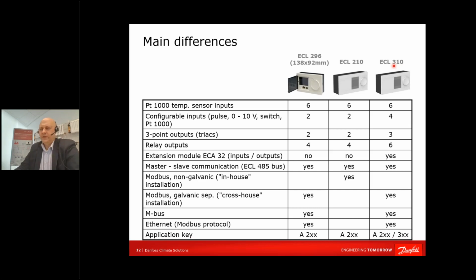Here, some can ask how many circuits ECL can control. The 3 stands for three circuits. The 10 means that it might control something a little bit more, like maybe a tank for domestic hot water. So you may say 3.5 circuits. Of course, you can control just one circuit with that controller. Then 210 was dedicated to the most common solutions like heating and domestic hot water, therefore two circuits.